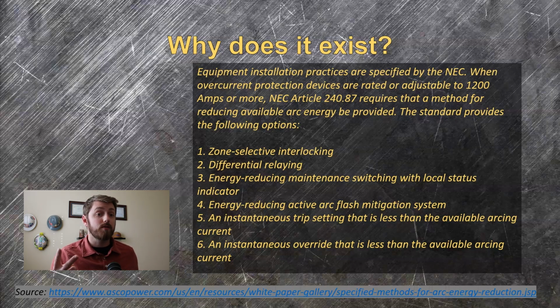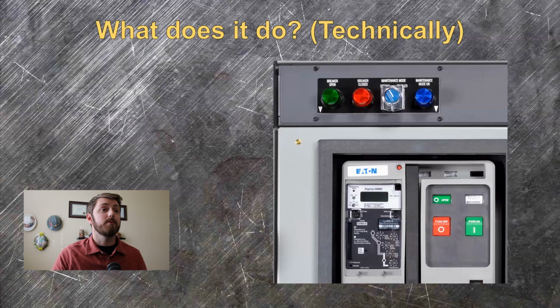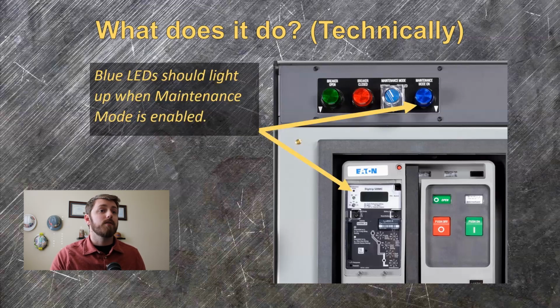Sometimes you'll see two arc flash stickers, one with maintenance mode on and one with it off. For the most part, to activate maintenance mode, you'll simply turn on the blue maintenance mode switch, which sends an input to the affected breaker. This is usually the main breaker on a switchboard, but can be multiple feeder circuits that activate all at once on large switchgear. You'll need to verify that the blue LED illuminates, and if you can, verify that the trip unit of the breaker you're enabling it on goes into maintenance mode as well.